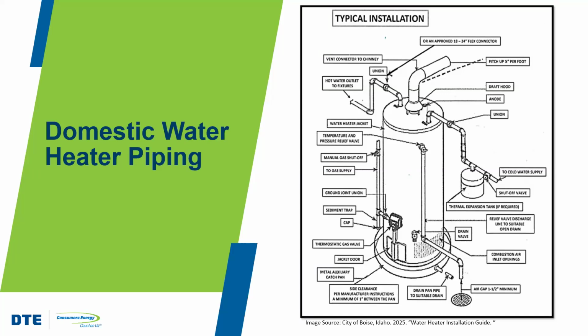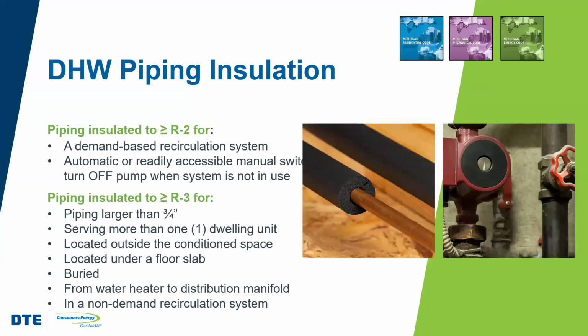The same criteria apply for shut-off valves. We don't want a shut-off valve between the relief valve and the valve termination. We don't want a valve, or anything between the relief and the tank or between the relief and the equipment, that would hinder its operation, right? And similar to boilers, we want those relief valves to terminate off the finished floor. So, not directly into the drain, but about 4 inches higher above that, so that it has free flow.